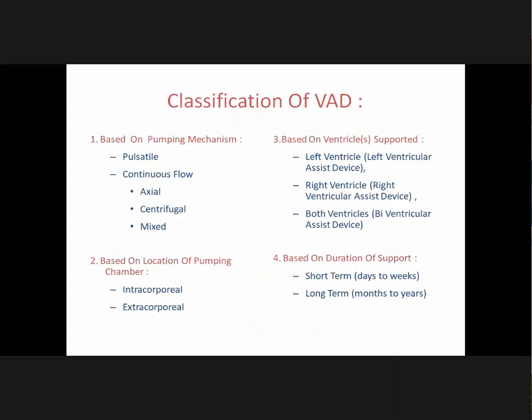Classification of VADs is based on four categories: pumping mechanism — pulsatile or continuous flow (axial, centrifugal, or mixed); location of pumping chamber — intracorporeal or extracorporeal; ventricle supported — LVAD, RVAD, or biventricular; and duration of support — short term (days to weeks) or long term (months to years).